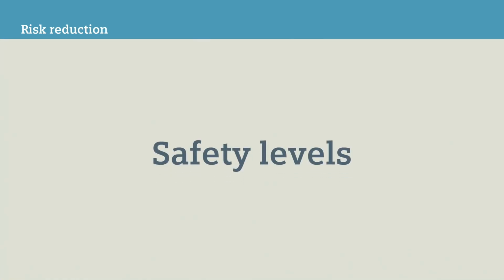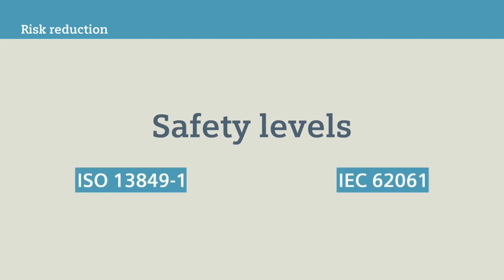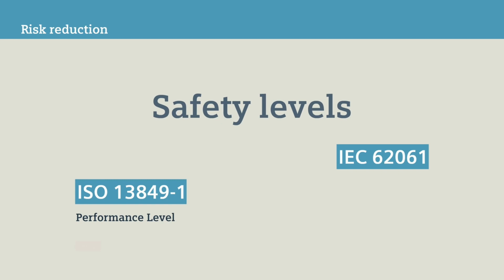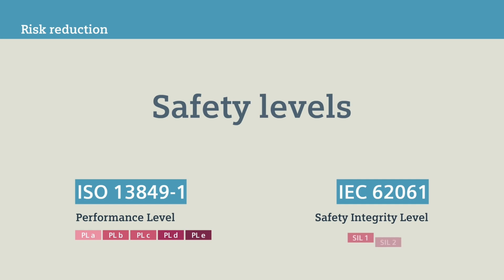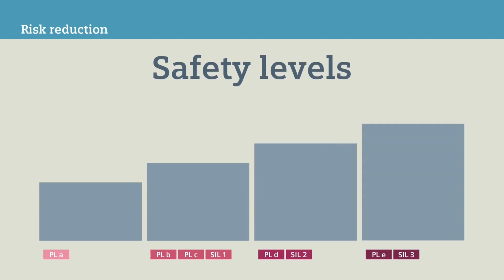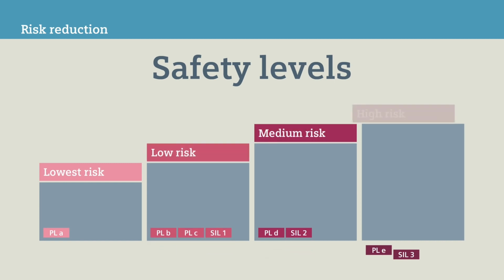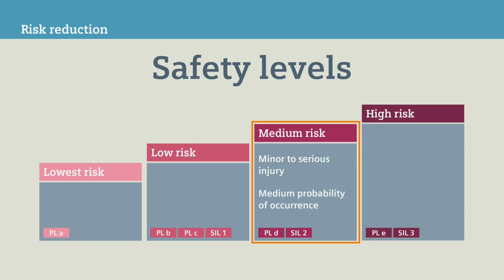Now determine, depending on the original risk, a certain safety level. You can apply two different standards. The ISO 13849 Part 1 standard defines the performance level PL in the gradations A to E. On the other hand, the IEC 62061 standard uses the term Safety Integrity Level, short SIL 1, SIL 2, and SIL 3. Here to clarify is a graphic comparison of the two levels in 4 different risk categories. For the safety door on our machine, the performance level PLD, or the safety integrity level SIL 2, is determined.